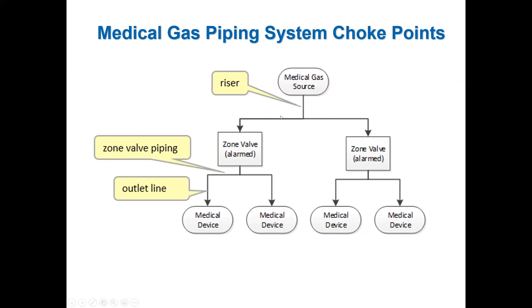So each one of these areas represents a choke point that must be evaluated to determine what the actual capacity is. So for example, if you're talking about tanks, banks of compressed gas, then your choke point or your concern or your risk is insufficient supply. Whereas if you're talking about liquid oxygen in this case, and by the way, air is usually not the problem. Air is usually not the limiting factor. It's mostly oxygen in my experience.